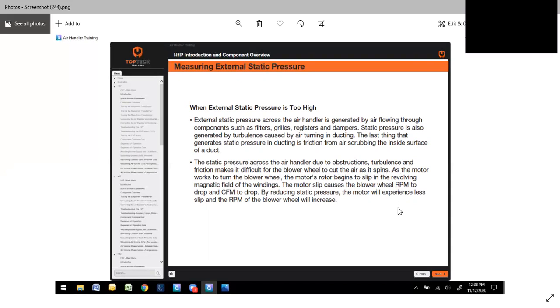As the motor works to turn the blower wheel, the motor rotor begins to slip in the revolving magnetic field of the windings. The motor slip causes the blower wheel RPM to actually drop and the CFM to drop. So by reducing the static pressure, the motor will experience less slip and the RPM of the blower will increase. So ironically, you can keep ramping that motor up, keep restricting it, and you'll actually cause your airflow to drop. That's even more pronounced with the constant torques and the ECMs.